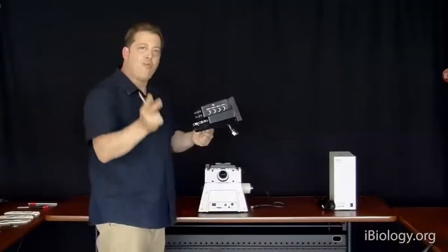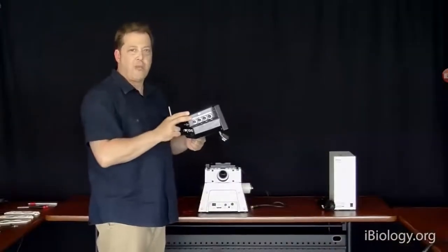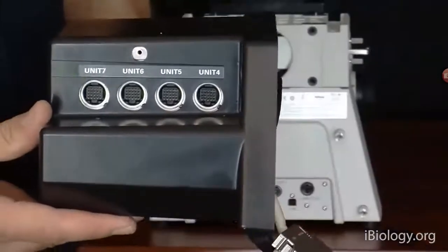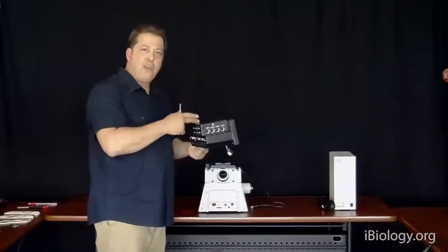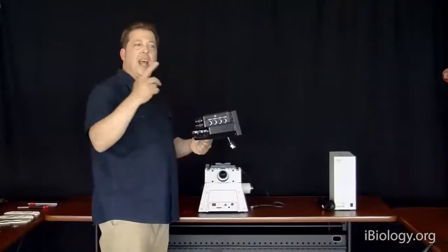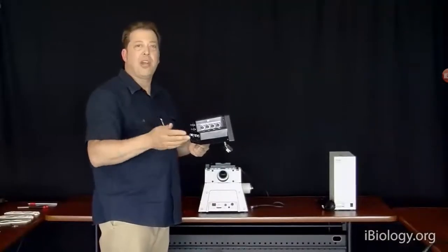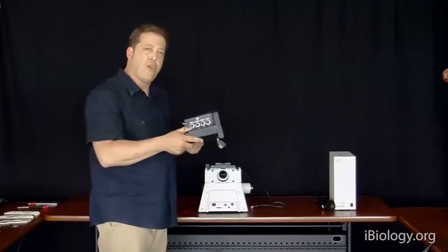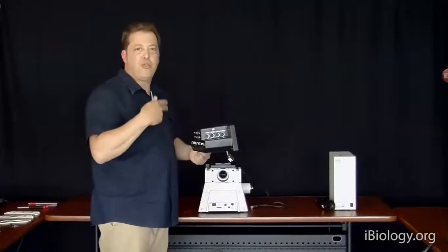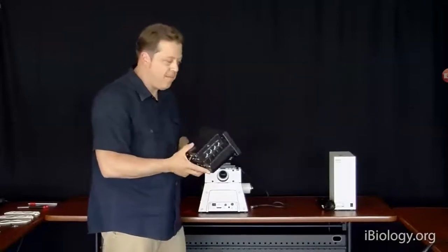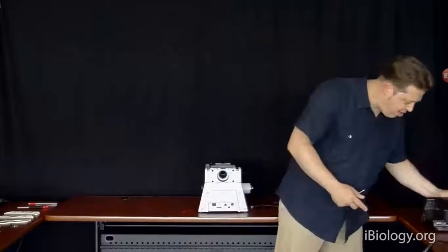And the hub controller then runs all the electronics on the microscope locally, rather than communicating back and forth with the computer saying, open a shutter. Okay, the shutter's open. That type of communication could take a long time. By doing it all locally, we can actually achieve much higher speeds on the microscope to do different imaging sequences. So we'll place this here.